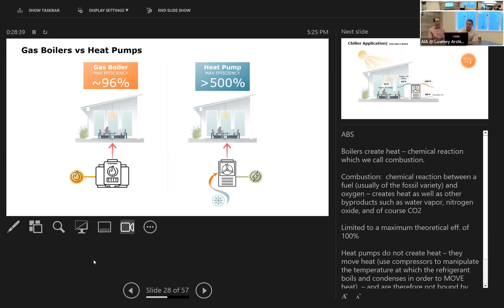A heat pump is a different animal altogether. It doesn't create heat in the way that a boiler does. It moves heat. Electricity goes into a compressor, and that manipulates the boiling and condensing points of the refrigerant, and that's what enables you to move the heat around. I'm not going any further than that. But suffice to say, it's under a completely different set of thermodynamic laws to combustion. Because of that, you can get a heat pump that is 300, 400, 500% efficient. What I mean by that is you can put 1 kilowatt worth of electricity into the heat pump and get 3, 4, or 5 kilowatts worth of heat out of the other side. We call that the coefficient of performance. So if you put 1 kilowatt of power into a heat pump and you get 4 kilowatts of heat out, you would say that heat pump has a coefficient of performance of 4.